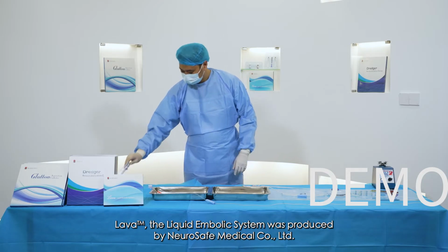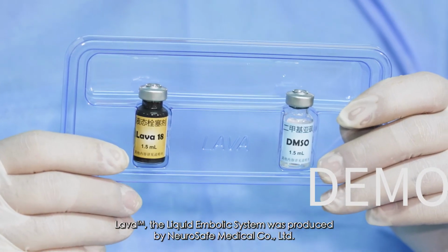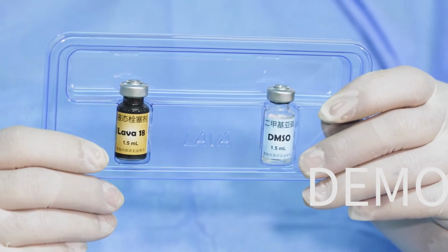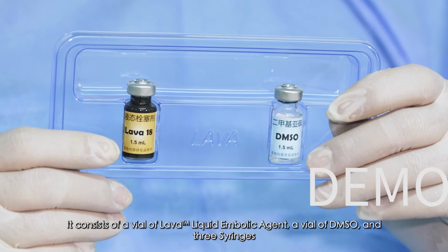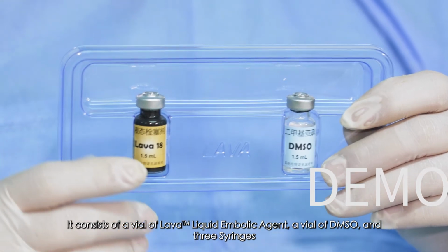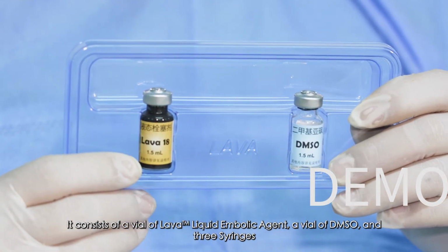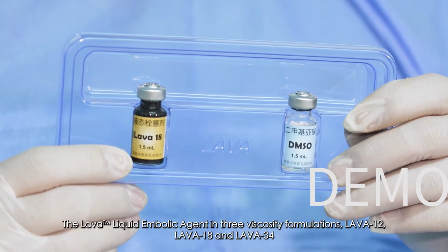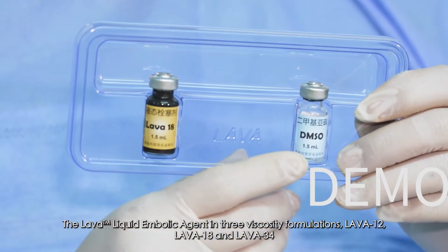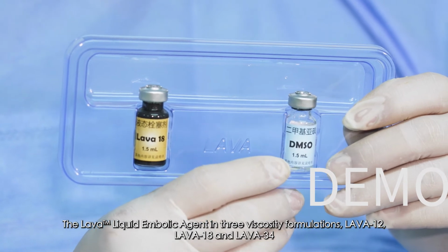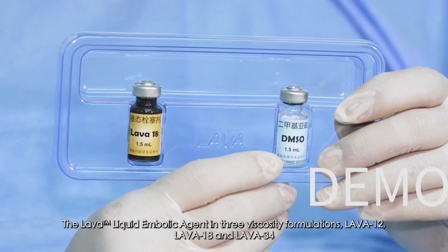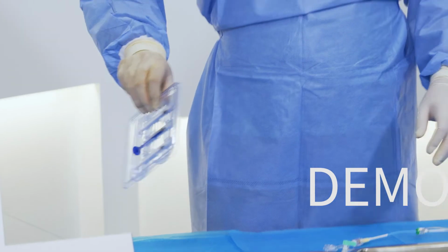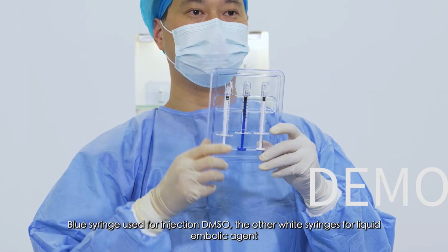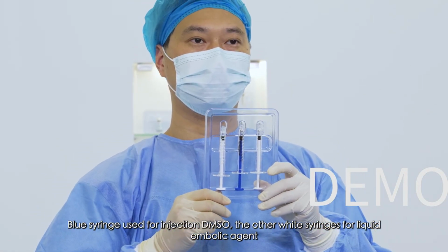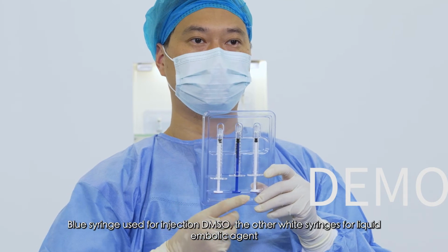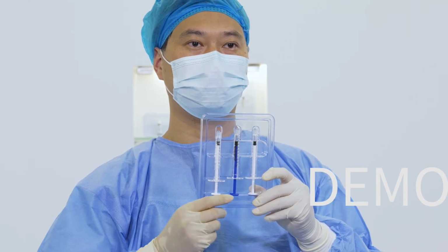LAVA, the Liquid Embolic System, was produced by NeuroSafe Medical Co. Limited. It consists of a vial of LAVA liquid embolic agent, a vial of DMSO, and 3 syringes. The LAVA liquid embolic agent comes in 3 viscosity formulations: LAVA 12, LAVA 18, and LAVA 34. The blue syringe is used for injecting DMSO, and the other white syringes for the liquid embolic agent.